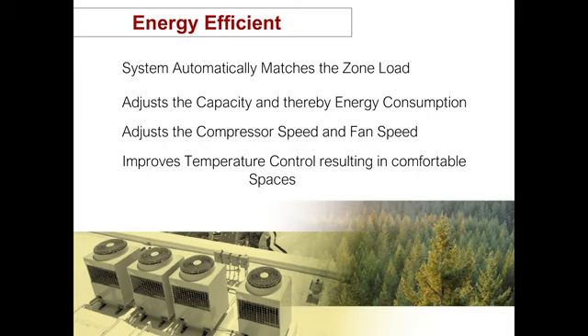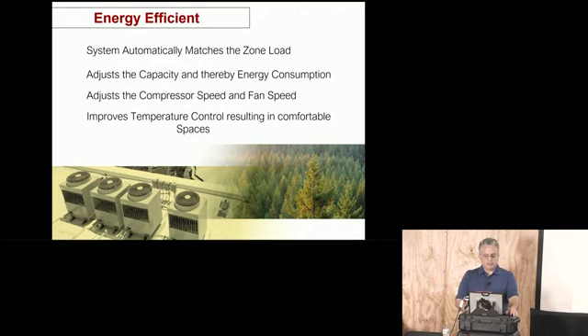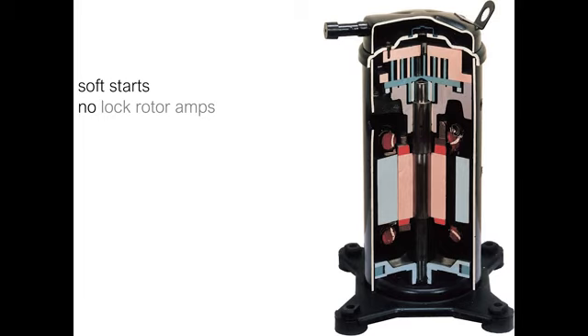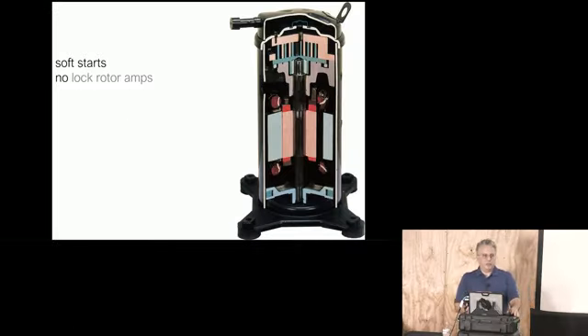So energy efficient. The system automatically matches the zone load, adjusts the capacity and thereby energy consumption, adjusts the compressor and fan speed, improves temperature control, resulting in more comfortable spaces. So soft starts. If you're working with any solar people, this is one of the reasons why mini splits are so popular with them, because when you design a solar system, you're looking at all the loads, and the locked rotor induction motor is going to be a big load. Could be 30% of the load. So solar guys love us.